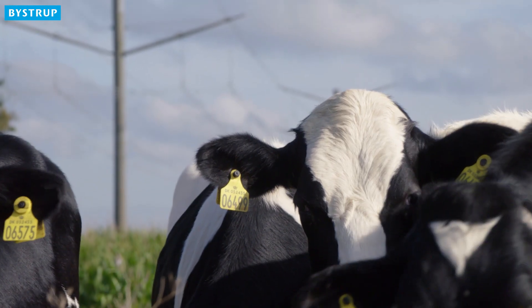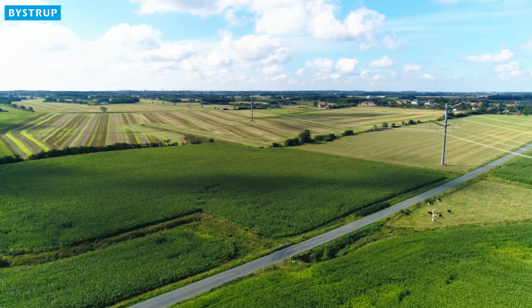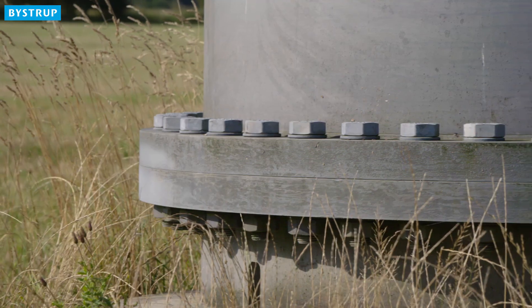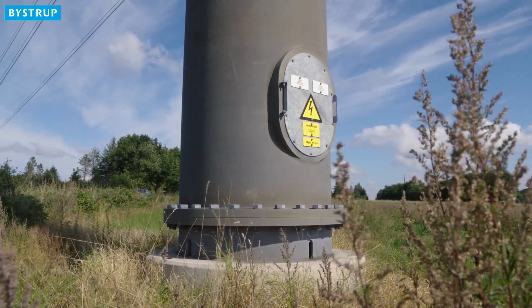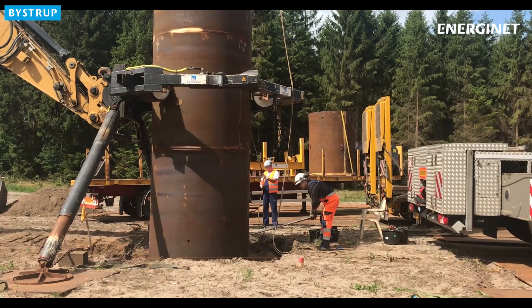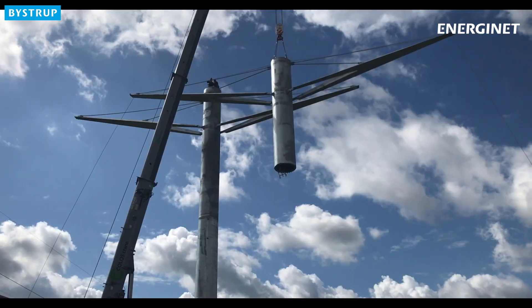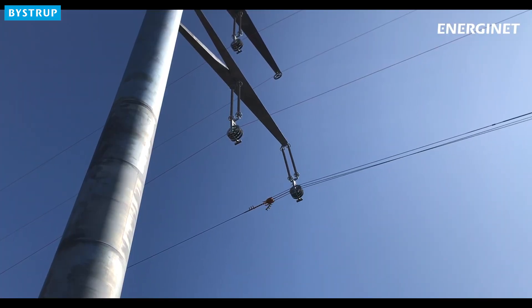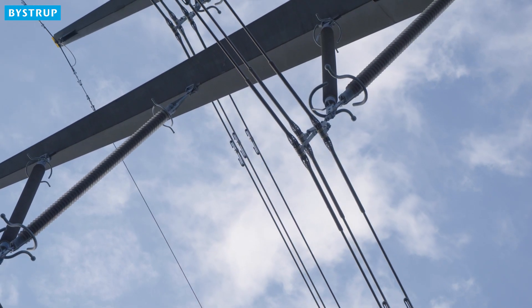The Eagle tower design is superior to the lattice tower in many ways. The footprint is reduced to an area of only 3m², benefiting from a circular steel shaft. The installation process takes only one day through the use of a monopile foundation, reducing the entire operation to a rate of up to 2 pylons installed per day, compared to 21 days for one lattice tower. The new improved design also offers far better lightning protection compared to a lattice tower.